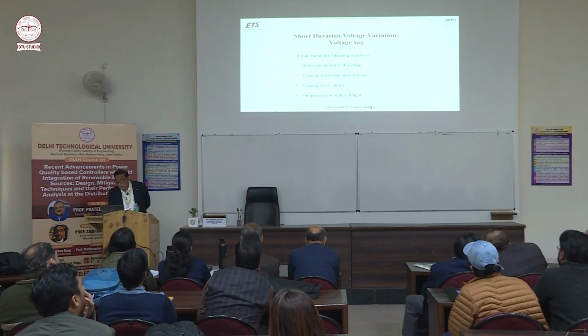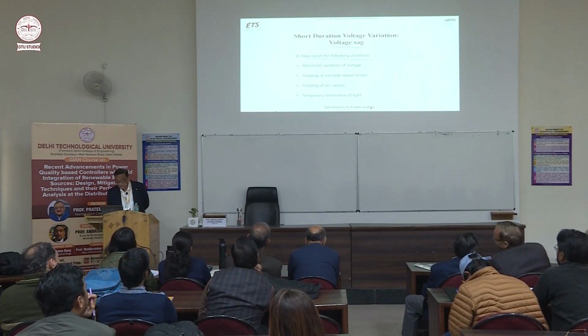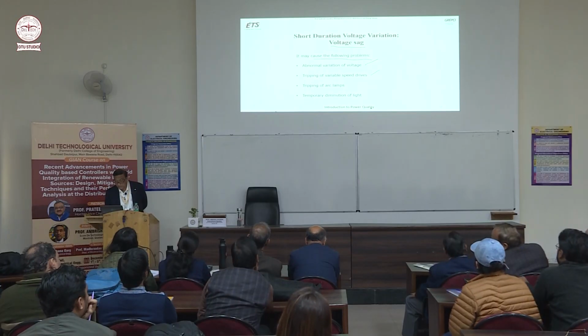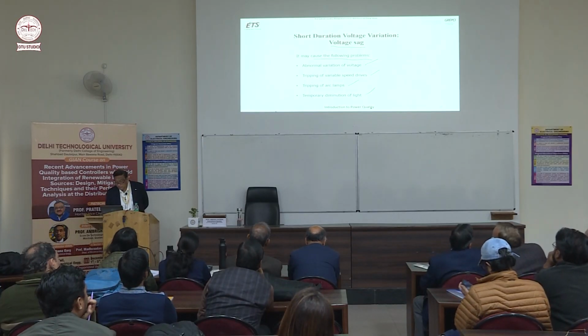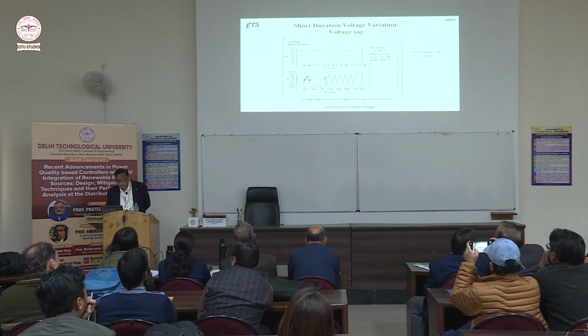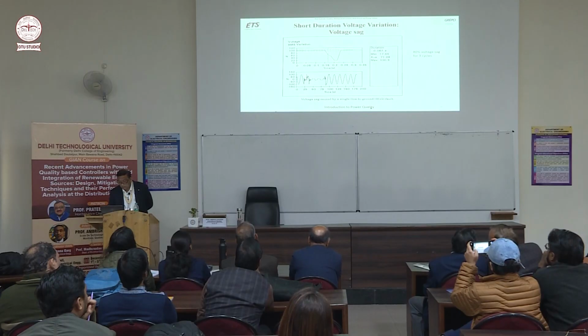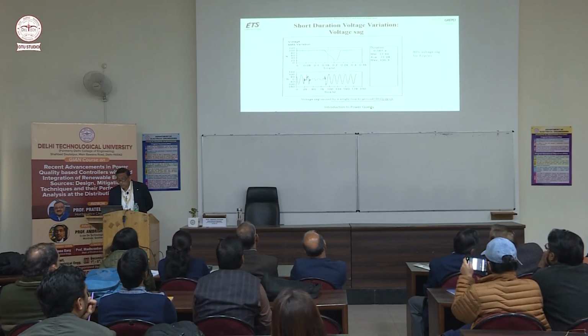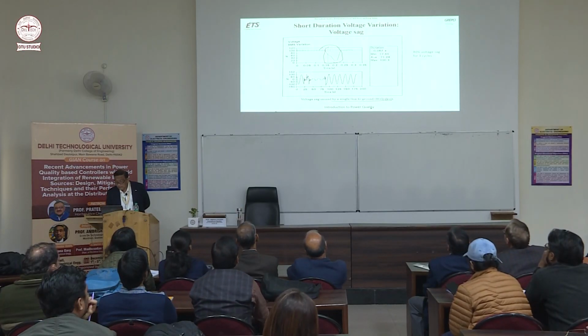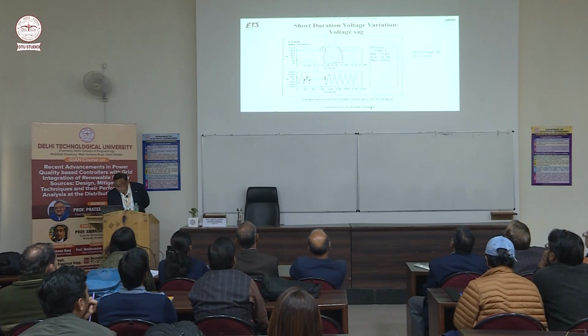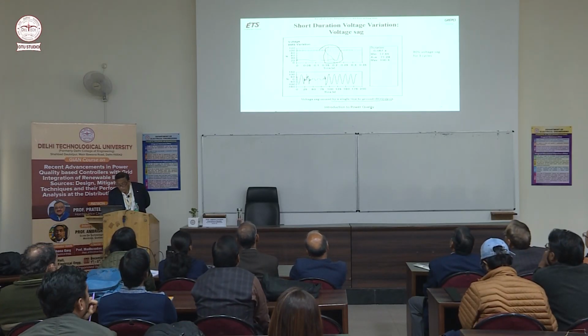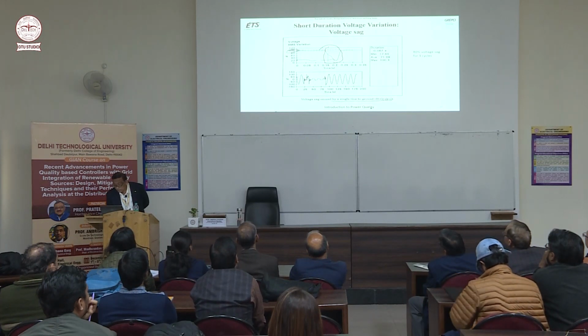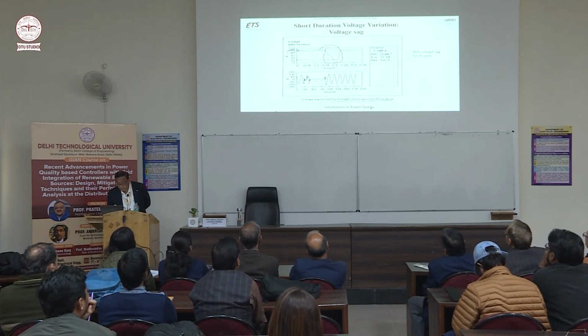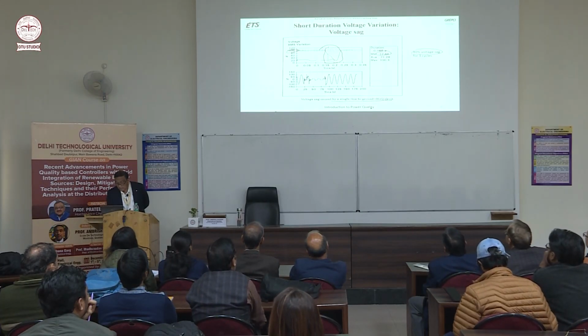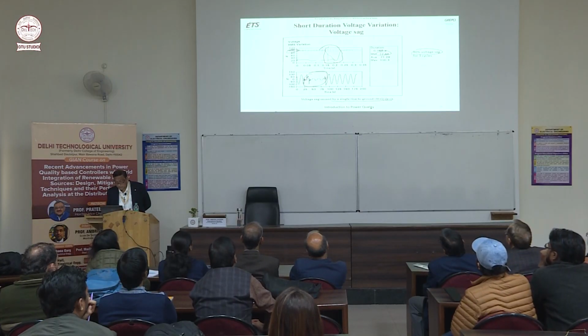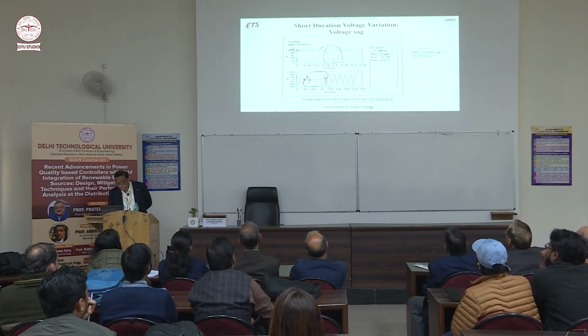Short duration voltage sag may cause the following problems: abnormal variation of voltage, tripping of variable speed drive, tripping of arc lamps, temporary diminution of light. So here you can see one example, voltage sag caused by a single line to ground fault. So you can see voltage sag, it's around 20% of voltage from around 100 volt. It came to a minimum of 17.44 volt. So it is around 80% voltage sag for around 3 cycles. So this is just an example of voltage sag caused by single line to ground fault.